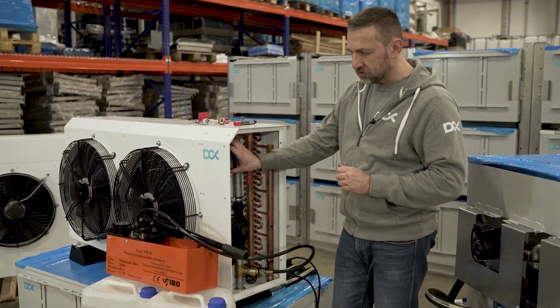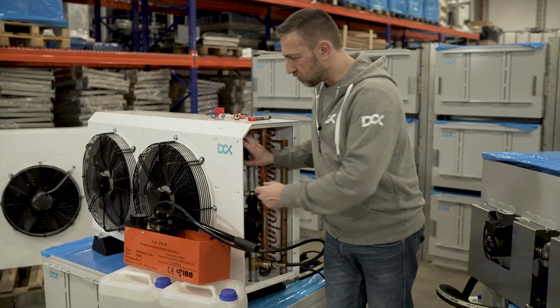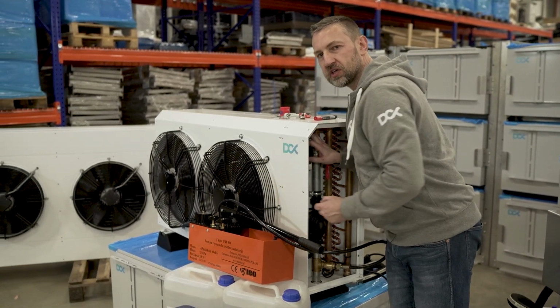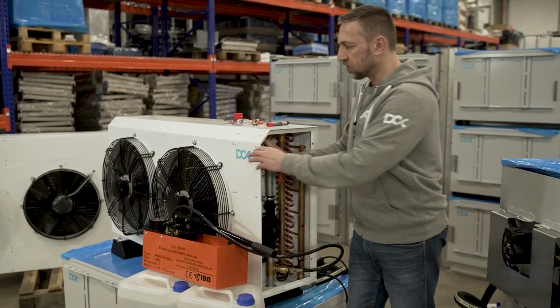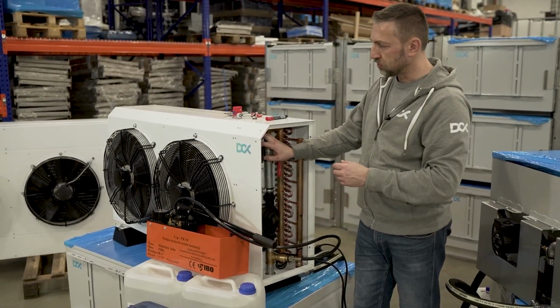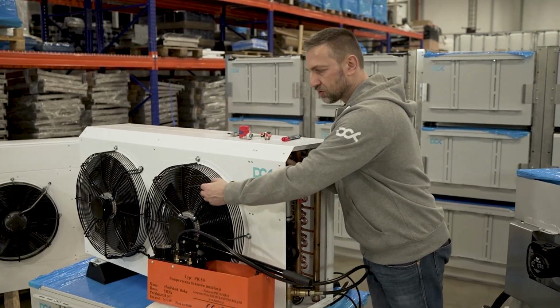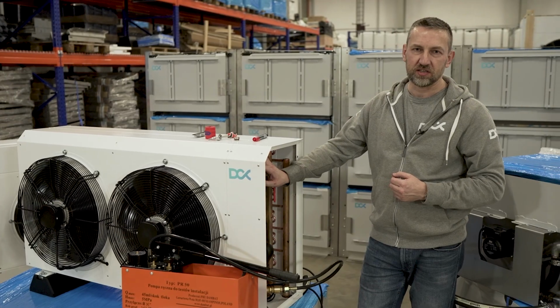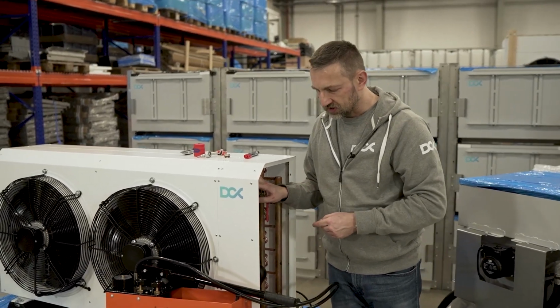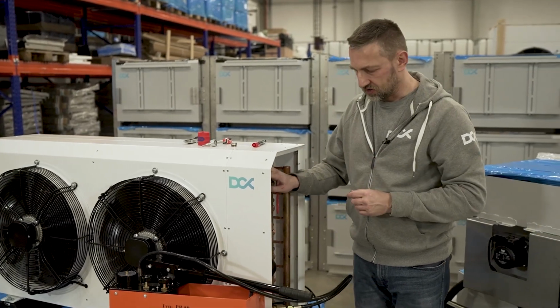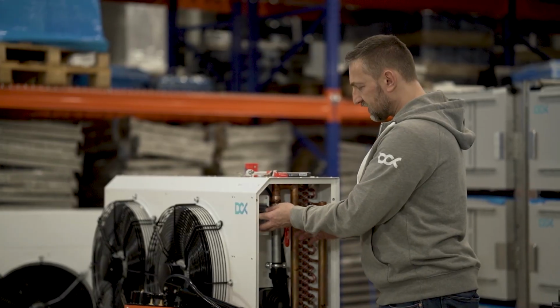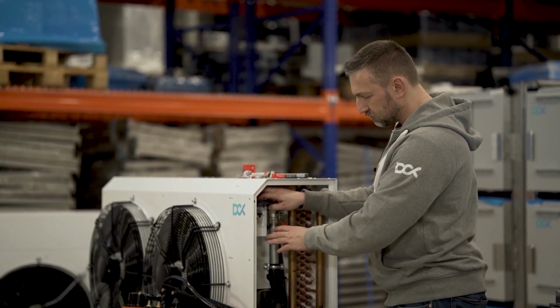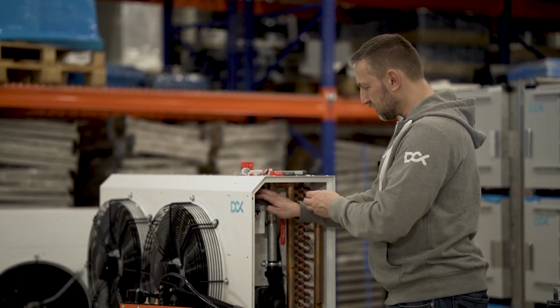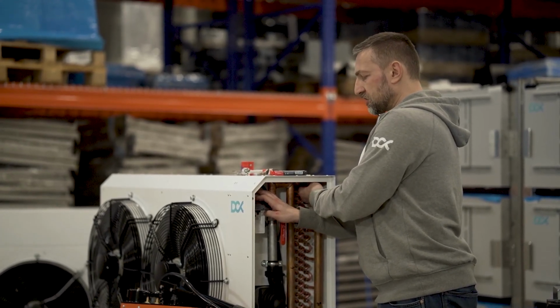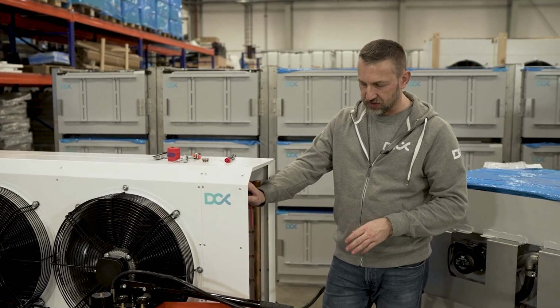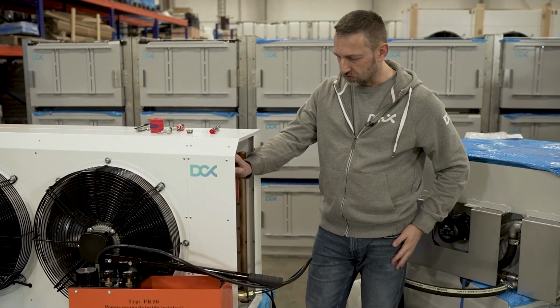And a pump which is set properly will show you 180, or nearby that number, on the pump head, which you are able to see through the first fan. So if you go here and observe the pump head, you will see the digits there, and there should be 180 or something like that. Now, since we closed the operation of the pump and we filled the system, it takes some time, but it's usually a one-time operation. Then we can go into the fans and start the fans and describe the operation modes of the fans.